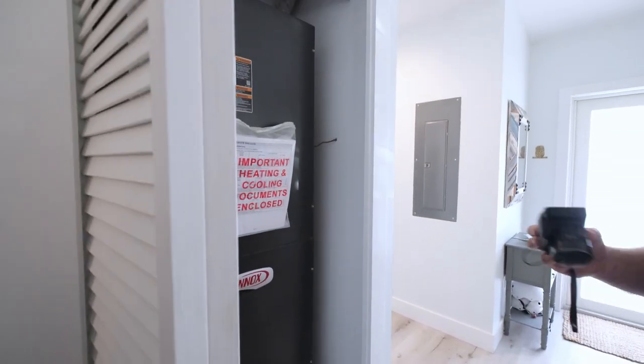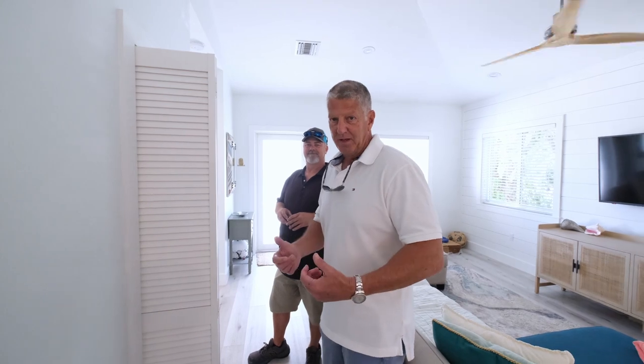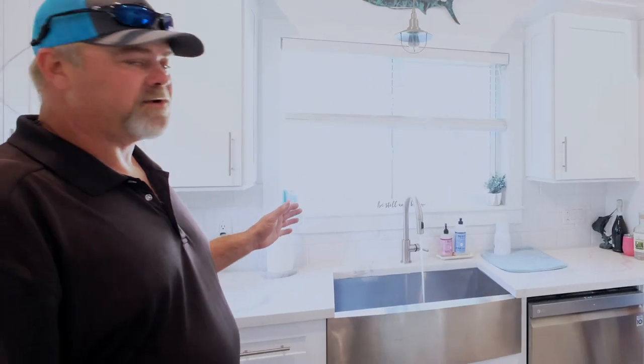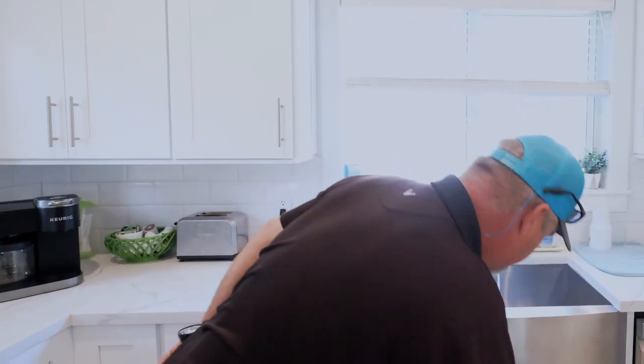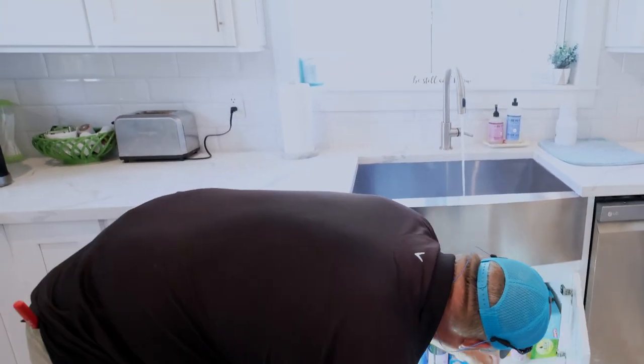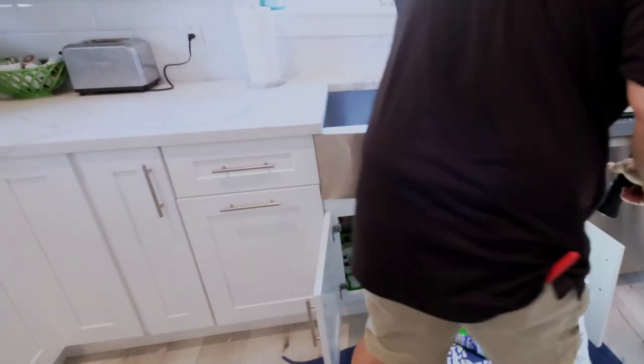If the air conditioner is running, we don't generally turn on the heater. Perfect — that's point one of the four-point inspection. The next thing we're going to look at is the plumbing. For the insurance company on the four-point, we want to check the plumbing, make sure there's good pressure. We check underneath the counter and take a look to see if anything's leaking on the drain side or the supply side.